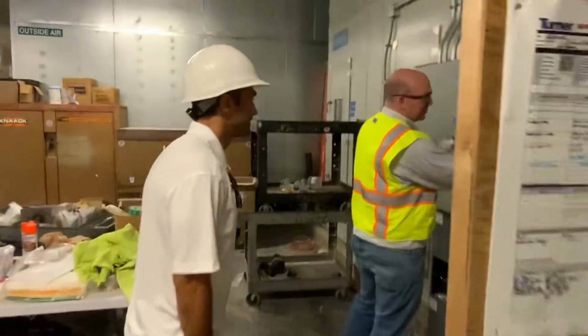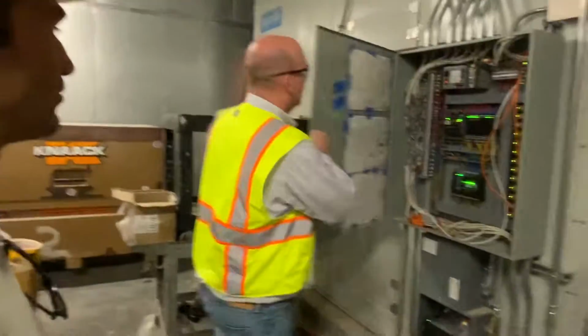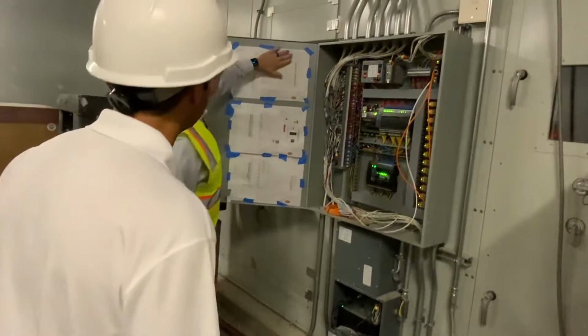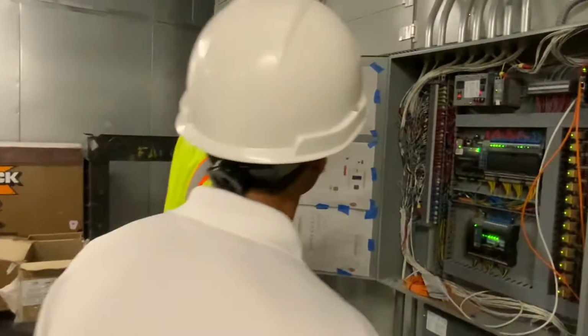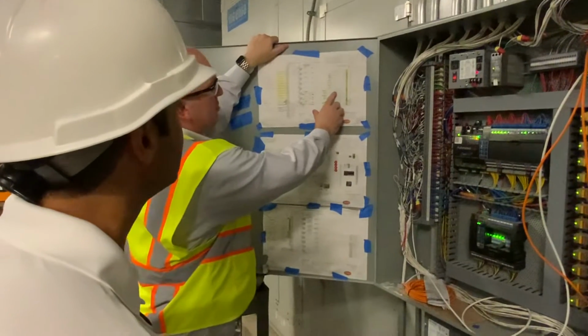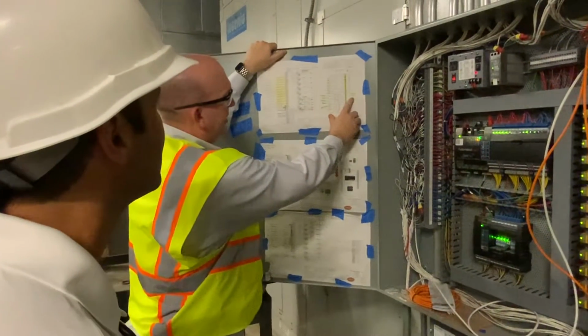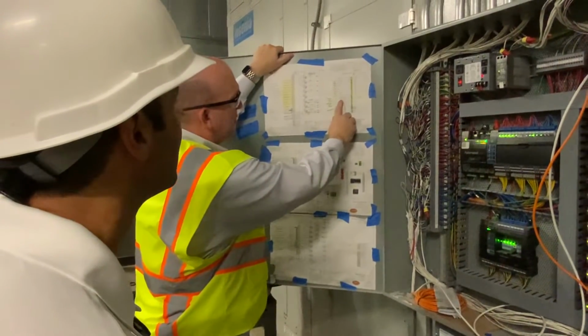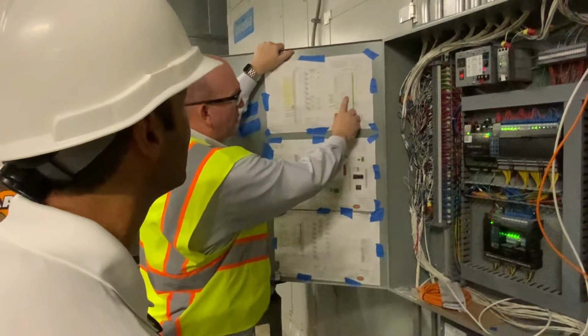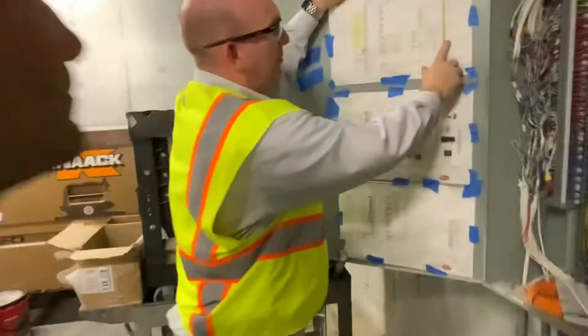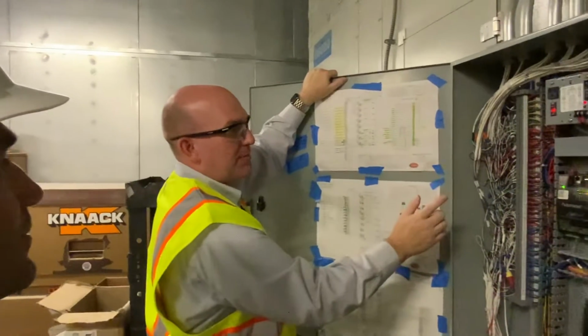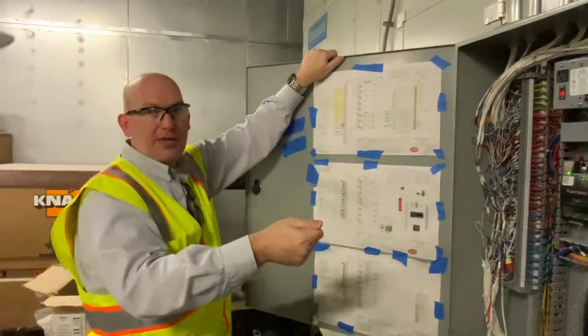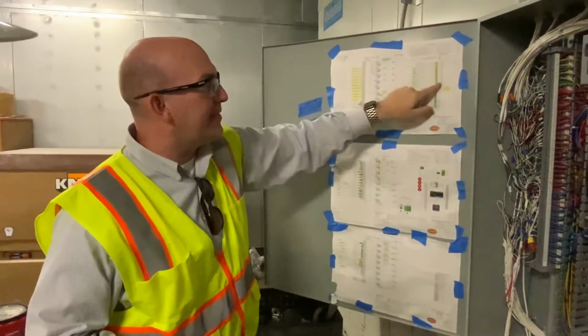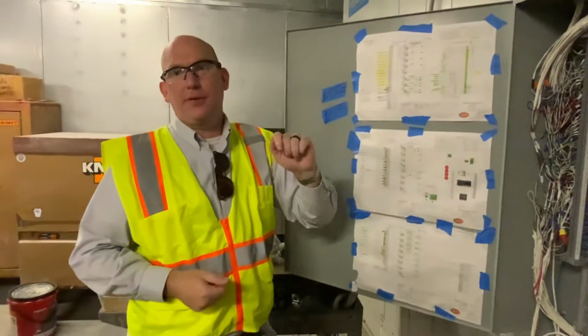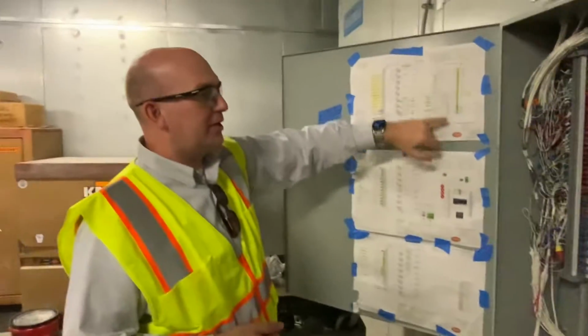No, I can try, but it's easier for me to show. Right. So here, what we have are those safety relays that are here that tie in, and then the damper motors are actually driven. We do control them, but they're driven by a ready to run from the VFD. Okay, so if you turn the VFD on, it closes a set of contacts, and then we power the motor and drive it open. So that's how each one individually knows.